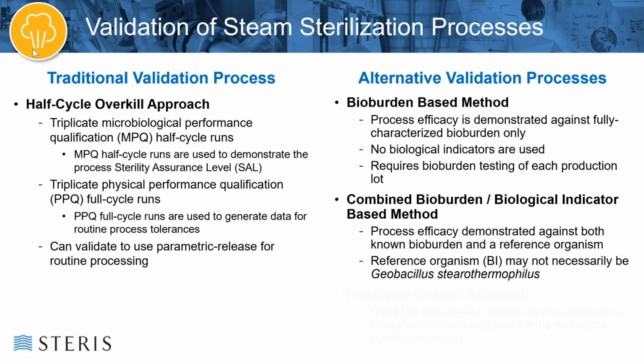So the previous slide, when we looked at 110 degrees C and we saw that 6.5 hour cycle, if we use a BI that is less resistant than Geobacillus stearothermophilus, we can actually bring that cycle back down to a manageable 30 to 60 minute process and still demonstrate an effective 6 log organism reduction during a half cycle, resulting in an SAL of 10 to the minus 6 or better, using that organism that's a little bit lower resistance.